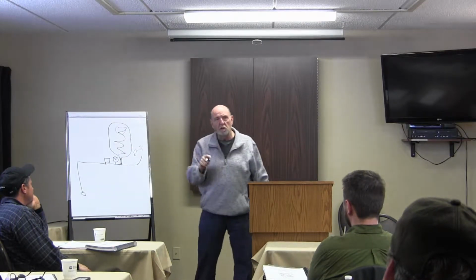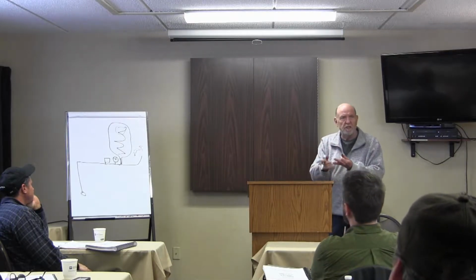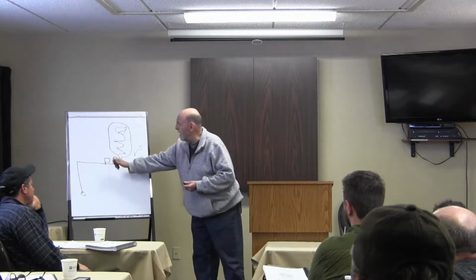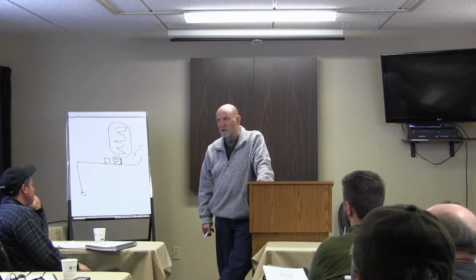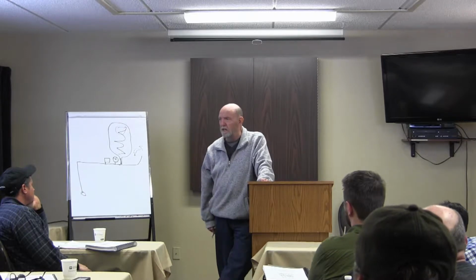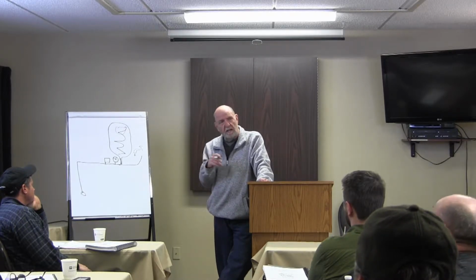And what you want to do as a home inspector is you're going to look at the condition. Is there rust? Is there cracked or broken hoses? Is it leaking? Get a general idea of the condition, and then time the clicks. So when you're doing your inspection, you literally, if you have a watch, look at it, or you're sitting there counting to 60 like I do. I hear a click, and I stand there looking at it. Sometimes your client walks down and wonders why you're staring at it, like you're thinking about something else. And I'm really just waiting for that other click.